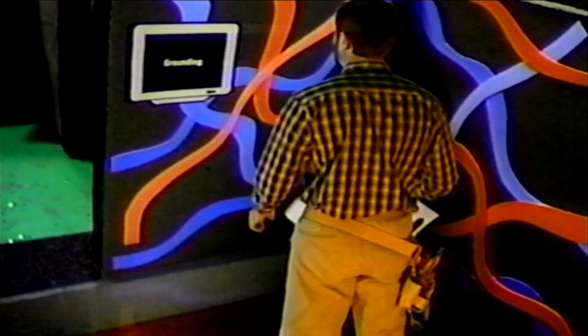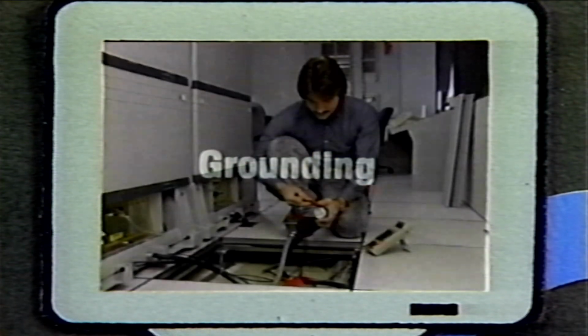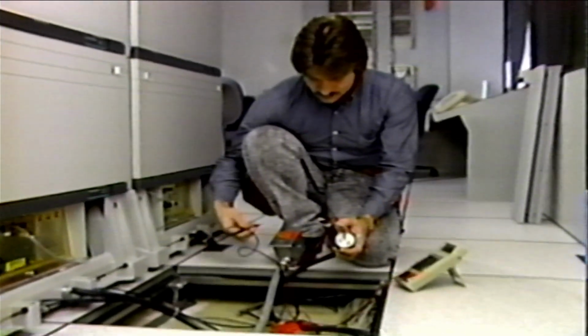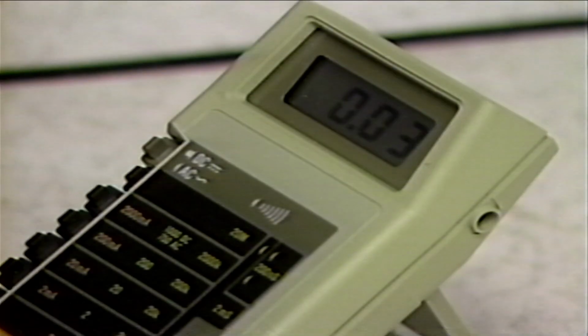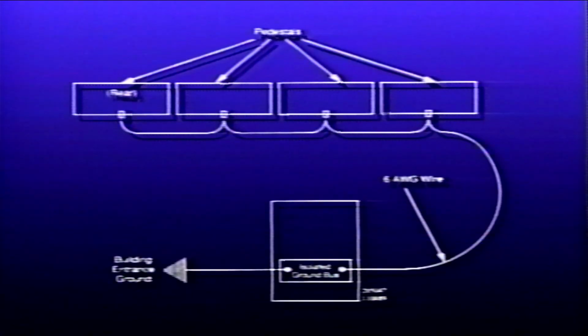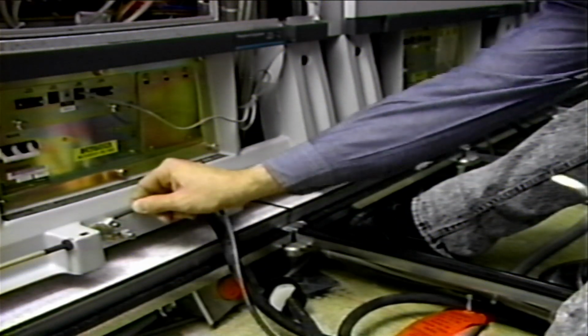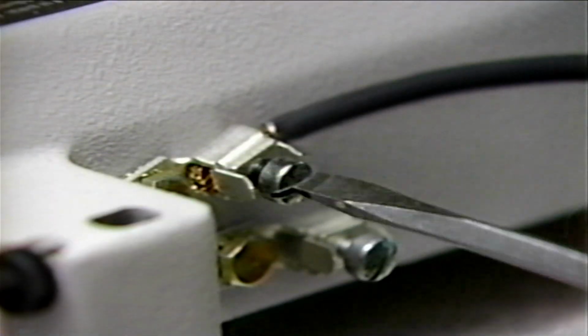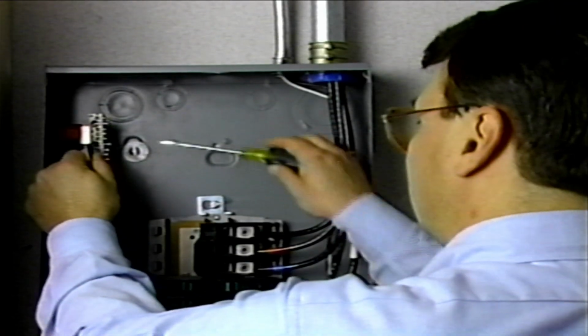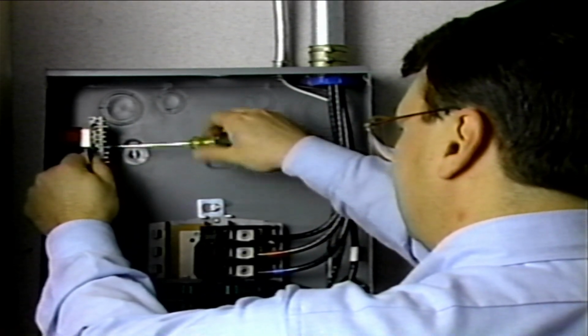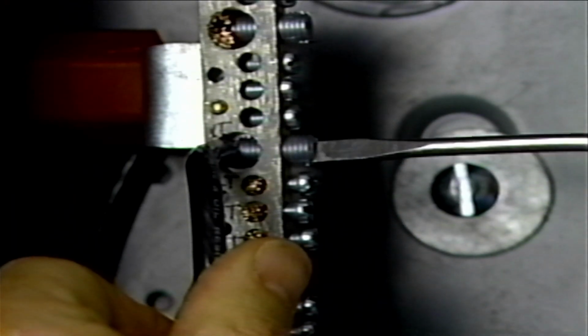Personnel hazard grounds must be installed on all equipment columns. Remember, failure to complete grounding tests properly can result in extremely unsafe conditions for personnel and serious damage to the system. Using the specified type of insulated wire, form a daisy chain of the ground lugs located in the pedestal of each column. Then, connect the last one to the isolated ground bus in the AC panel, using extreme caution.